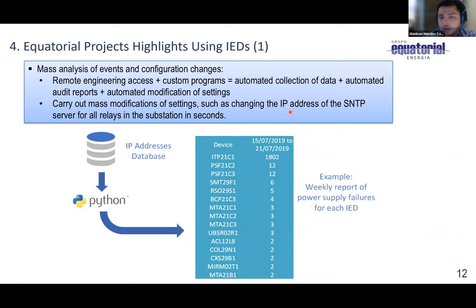This is an example of changing the settings. If you want to change the IP address of the SNTP server, we can do it in seconds on one relay. Another project that we have using this same data analysis is a database of IP addresses. We pass this information to a script made in Python, and the script will access all relays, retrieve all events, and count all supply failures for each IED. So we don't have to access the events manually and count each occurrence ourselves. The script can do it by itself.